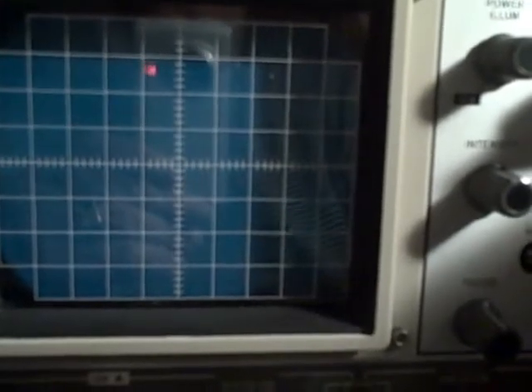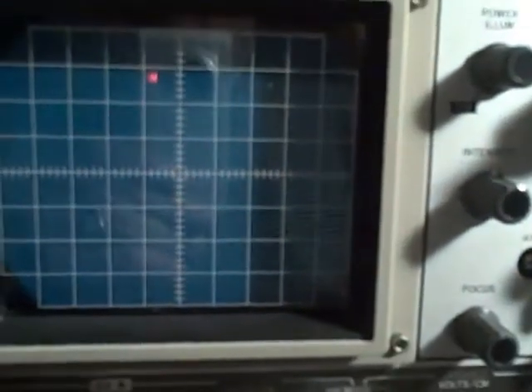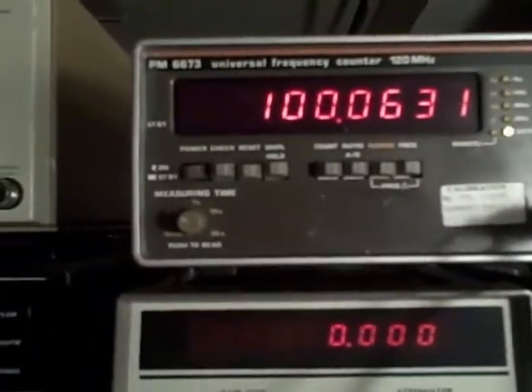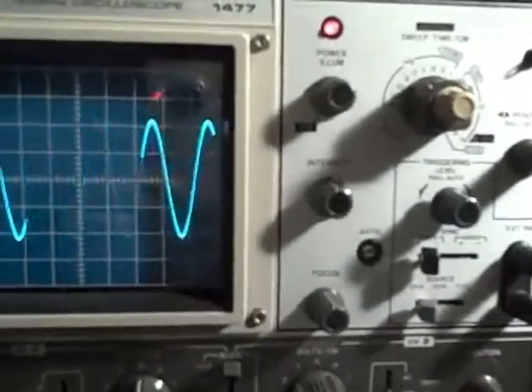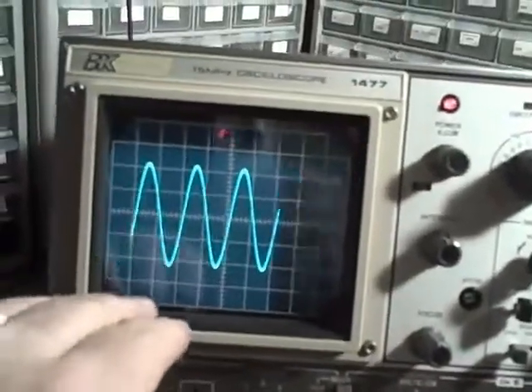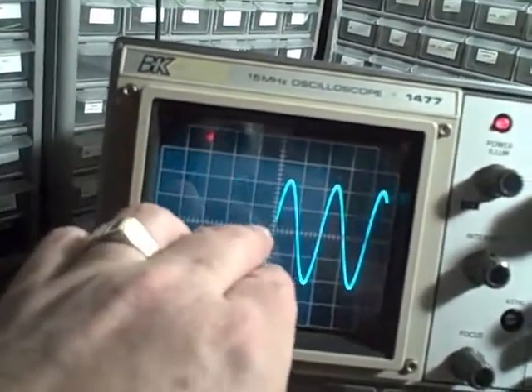At 10 milliseconds per division we see it takes ten divisions to make one full sweep, and it does. Now we're reading 100 Hz — 100.0 Hz. At 5 milliseconds per division we are seeing a full cycle in two divisions.